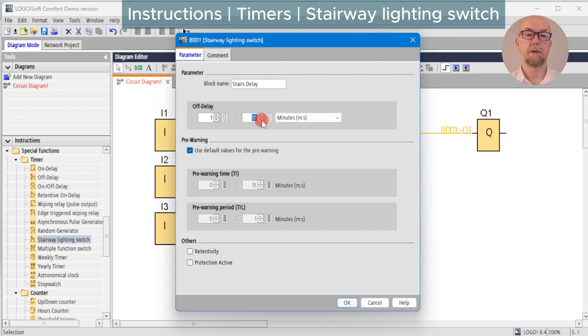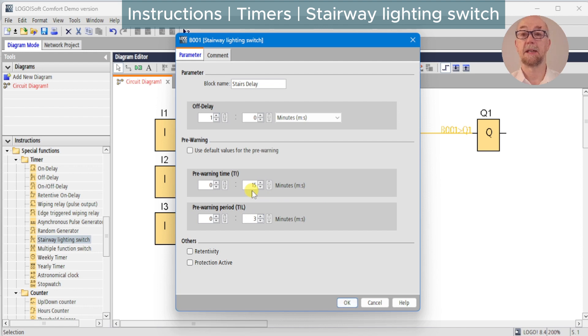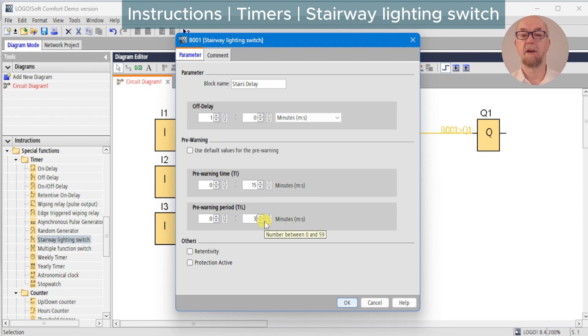We're going to extend the off time just so we can see. These two parameters set how long before the end we give a warning blink-off of the lights and how long that warning is for. In general, we want to allow enough time that the user could get half a flight of stairs and re-trigger the switch if they need more time, but short enough that it won't cause an accident.